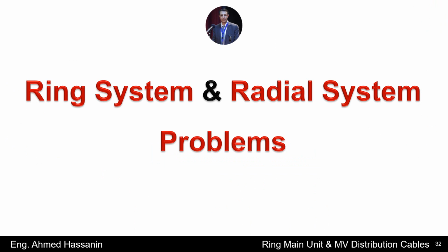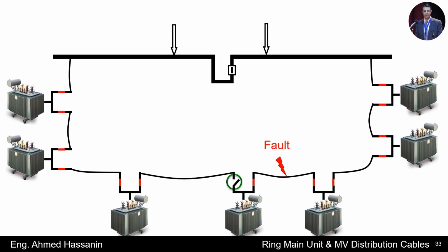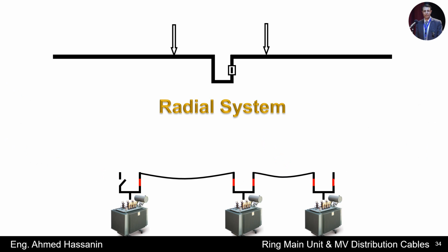I will talk about the most important problems in the ring and radial distribution systems. If any fault occurs in the ring distribution system, how can we repair this fault, or what are the correct steps to repair this fault in a short time to ensure the continuity of the electrical power to the loads and consumers? I will talk about the main components of the radial distribution system and the difference between it and the ring distribution system.